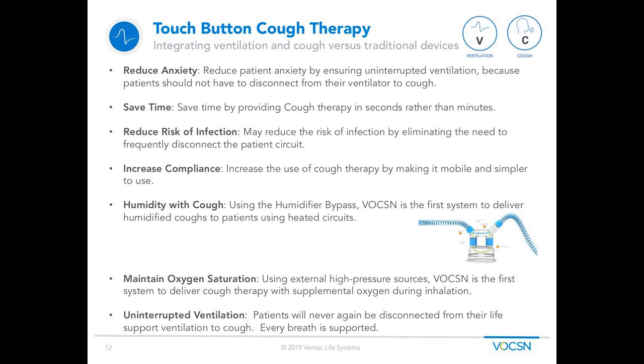You can also do humidity with a cough. This is an image of our humidifier bypass that allows the circuit to connect to the humidifier and lets you do cough therapy without pulling all of this water back to the ventilator during cough. We know humidified air is a good thing for some patients. However, when you go to do a cough with a separate device, you're doing it with dry, cold air because it can't be connected to the humidifier.